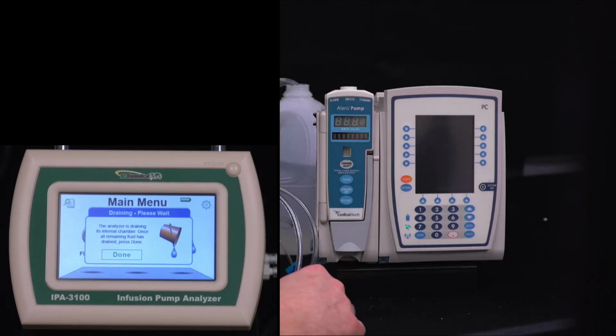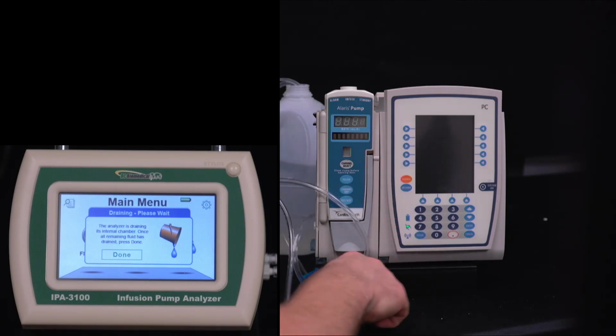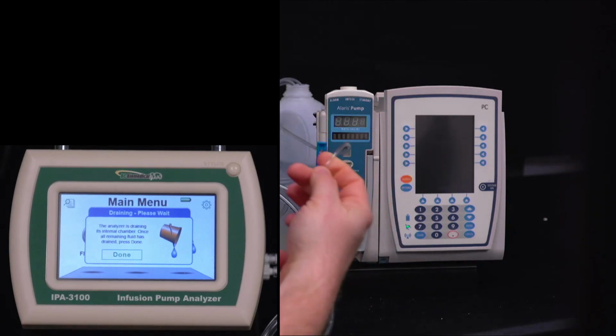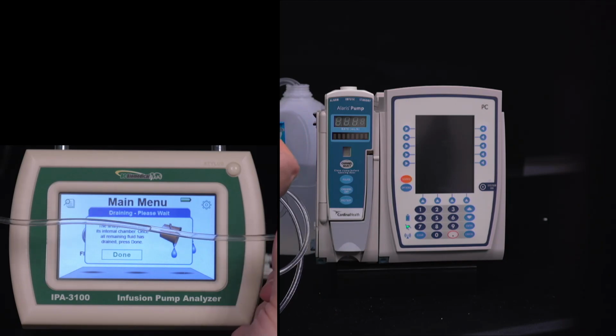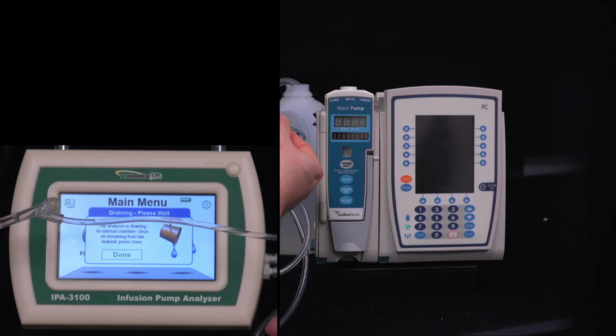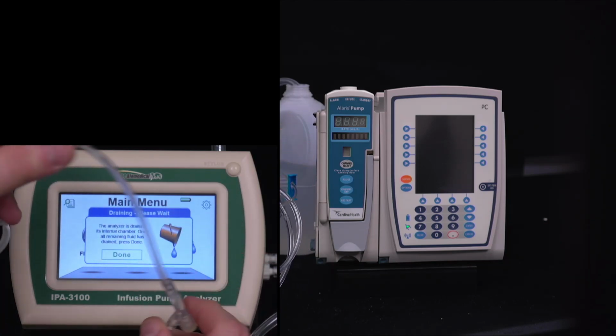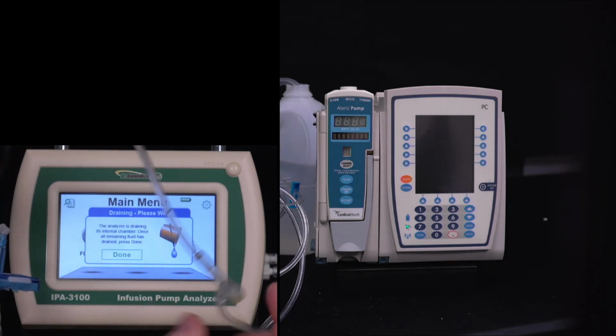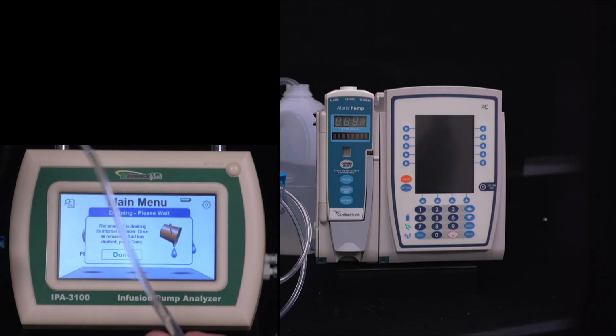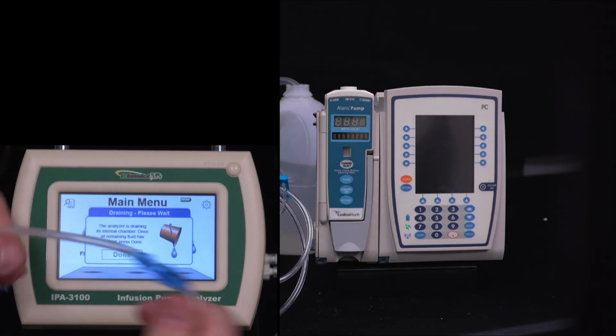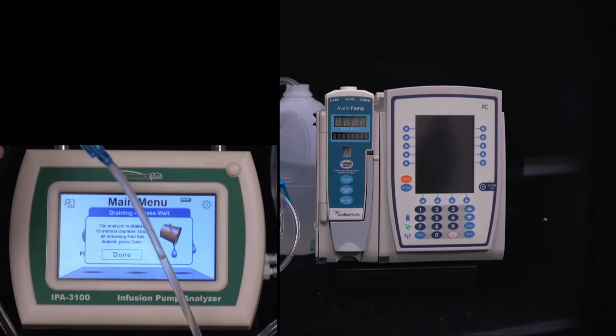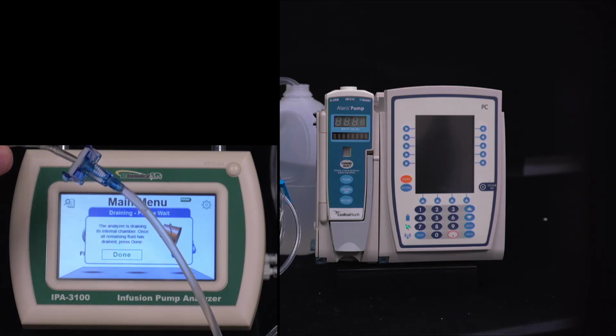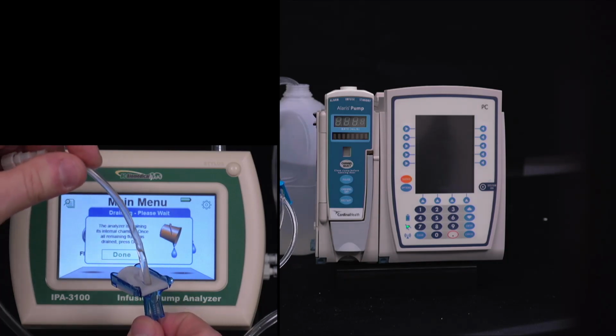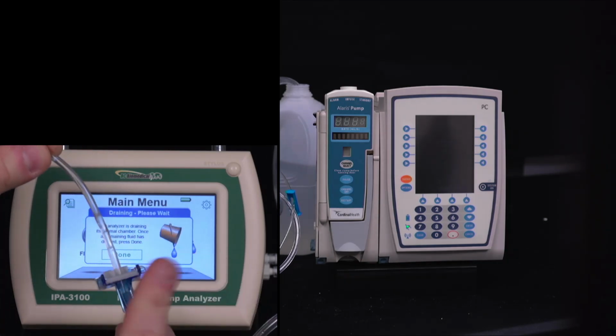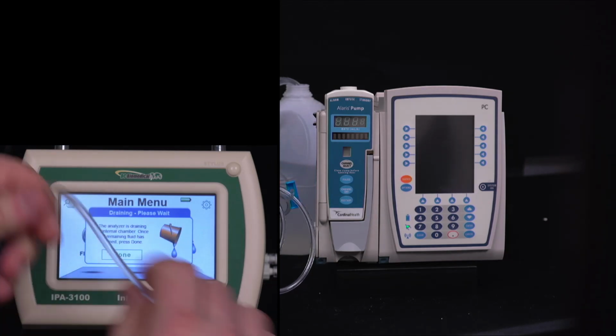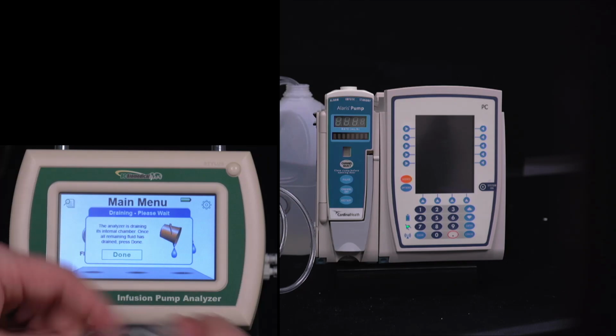Maybe the view can't see it there, but let me see if I can get this in the camera. So it's starting to pull that water through the tubing. It's almost at the administration set. Now what we want to do is obviously make sure that we get all the bubbles out. If you've tested an Alaris pump before, you know that it's quite sensitive to bubbles. Now the IPA 3100 is not. It really will ignore any bubbles, but for what we're going to do, we want to make sure that we don't get any bubble alarms. So those air pockets like to get trapped at anywhere there's a corner or a fitting.